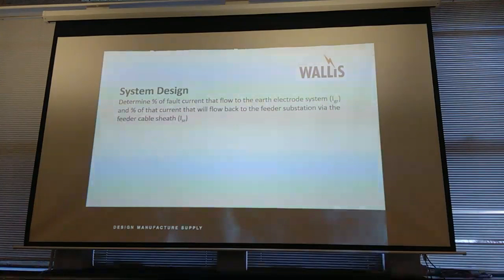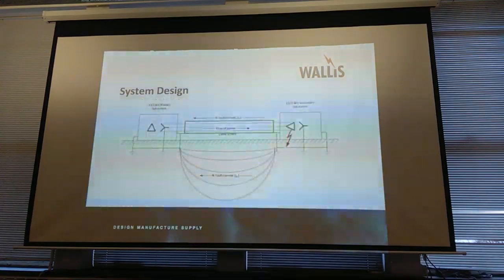System design, yeah. So again, coming back onto this, a percentage of the earth fault will flow to the earth system, and a percentage will go back by the cable sheath. Forgive my little sketches. I find them a damn sight easier to do this way and just demonstrate it than try to explain it sometimes. So as you can see, you've got the 33 to 11, and then your on-site 11 to 400 volt substation there. So this is what I'm saying.